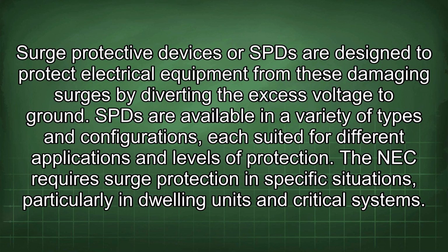Surge protective devices, or SPD, are designed to protect electrical equipment from these damaging surges by diverting the excess voltage to ground. SPD are available in a variety of types and configurations, each suited for different applications and levels of protection. The NEC requires surge protection in specific situations, particularly in dwelling units and critical systems.